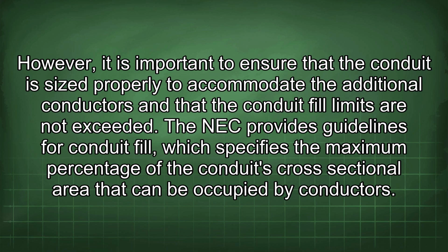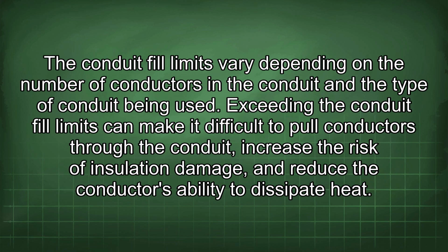The NEC provides guidelines for conduit fill, which specifies the maximum percentage of the conduit's cross-sectional area that can be occupied by conductors. The conduit fill limits vary depending on the number of conductors in the conduit and the type of conduit being used. Exceeding the conduit fill limits can make it difficult to pull conductors through the conduit, increase the risk of insulation damage, and reduce the conductor's ability to dissipate heat.